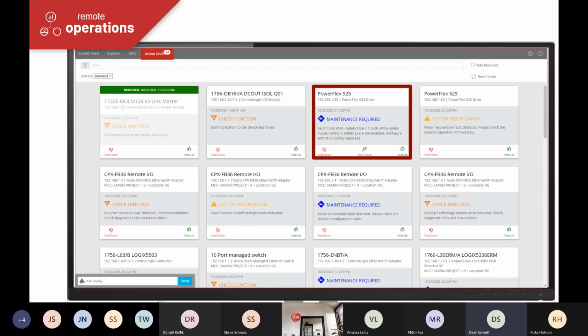In the red box there, you see a device called a PowerFlex 525, an AC drive, and it's producing data saying maintenance is required, there's some sort of fault on it. That took no programming by anybody, no systems integrators, no manufacturer. You just hang the device on the network, and this box sits on the network and automatically collects this data from smart devices.